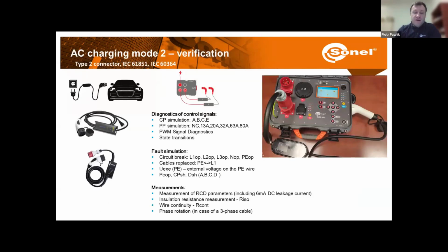Okay, so those were different types of chargers. Now let's look at the tests that we need to perform. So let's start with mode 2, when we are just having the cable that we will attach to the existing socket. So here for the cable, the measurements, as you can imagine, we are going to check the continuity and insulation resistance. We are going to check the RCDs on this cable. And in case we have a three-phase cable, we can also check phase rotation.